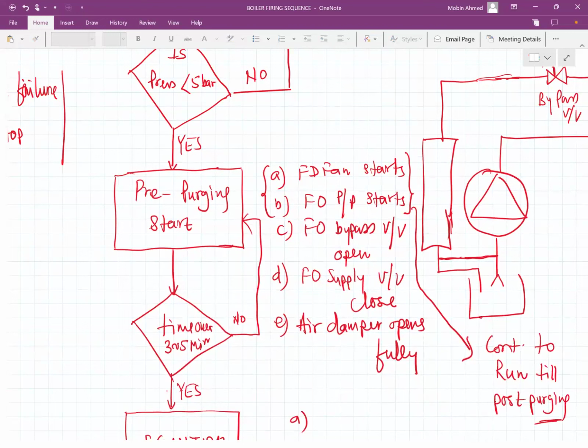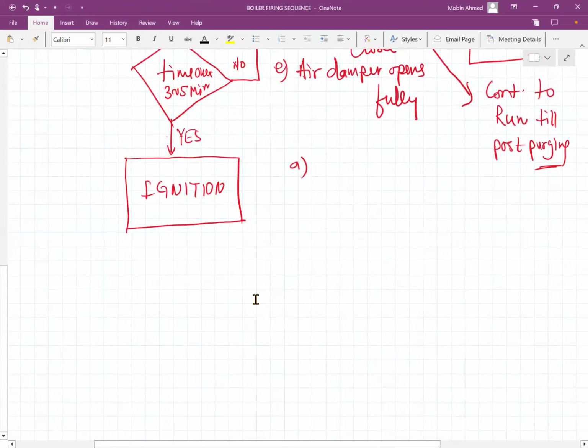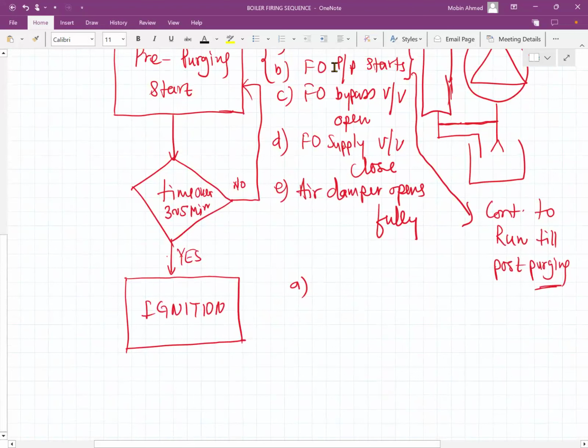Okay, post purging. At least FD fan will be running. FO pump is having again a timing. After a certain period of time, it will be off, but FD fan continues to run for the post purging. So these two are going to continue to run till the stop command comes. If it is tripping for any reason, these two are going to switch off, but FD fan still is going to run. Generally it runs unless you press the emergency stop. Then ignition. Now two things, FO pump and FD fan, that is running and it will run continuously. I will not be writing that one.